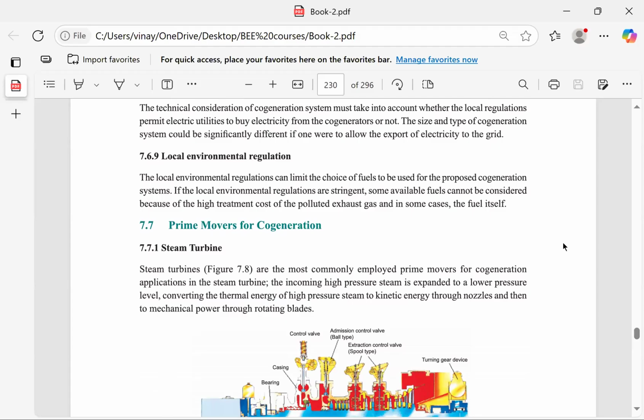For example, if I am burning rice husk or coconut shell as fuel, or biomass with slight moisture that gives off black smoke, the location of the factory and its environment matters. Depending on that, you will have to change your recommendations. If it's in the heart of a metro city, they may not allow you to use that fuel; they will say resort to natural gas instead, because then the pollution will be less. They won't allow you to burn coal or biomass that belches out black smoke. So these factors must be kept in mind when suggesting a retrofit or a new system.